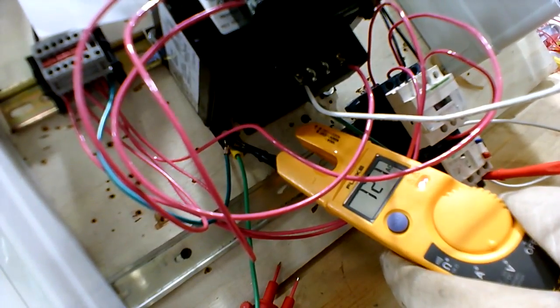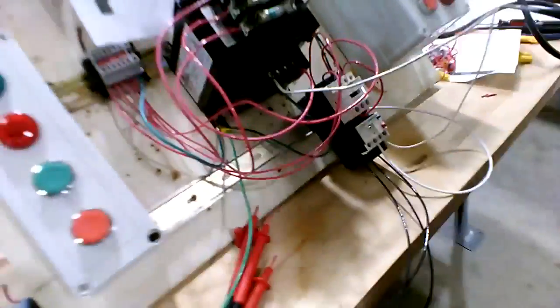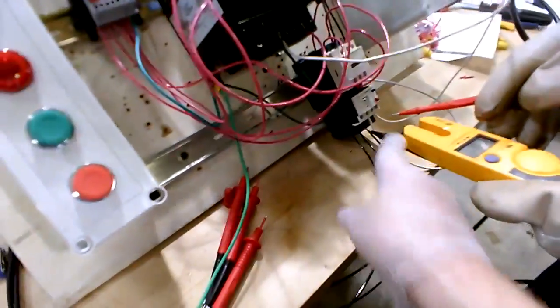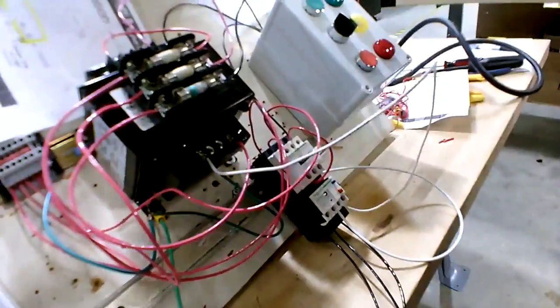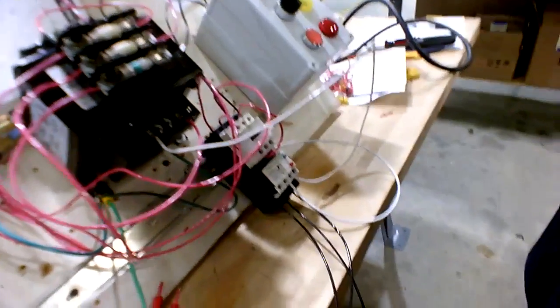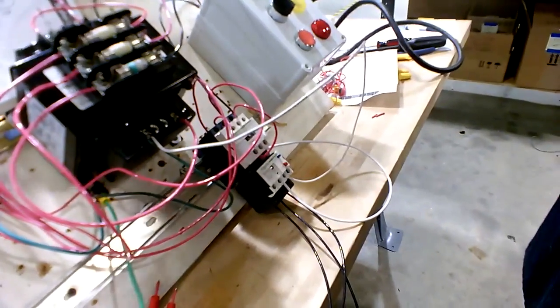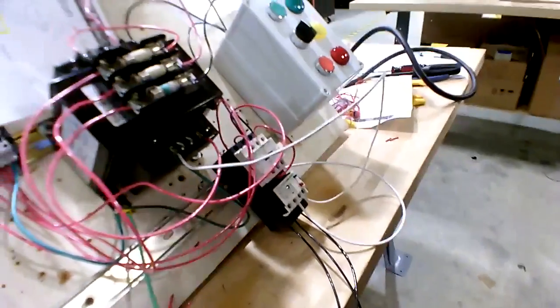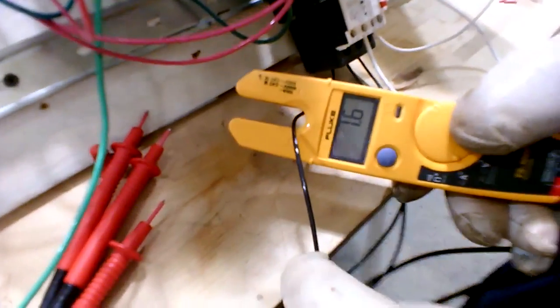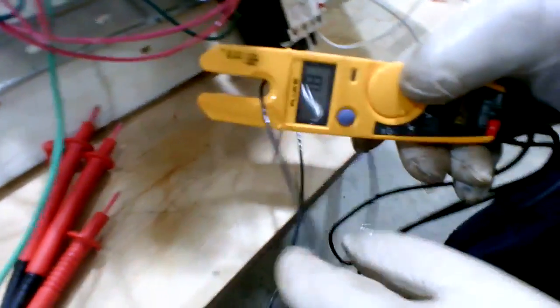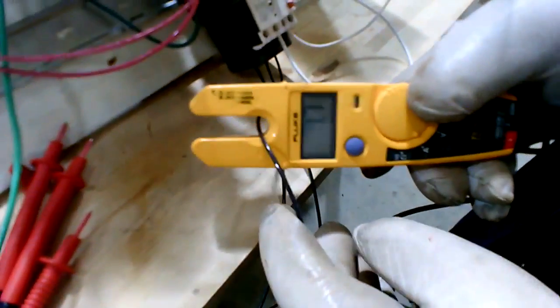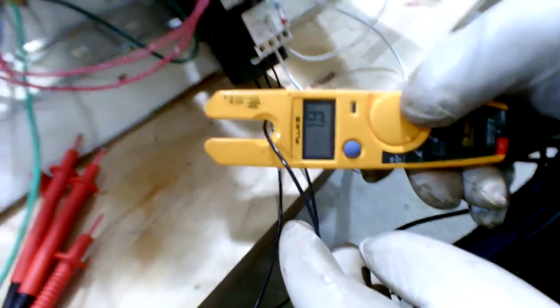That's correct. Now you're going to check the amps. So you checked voltage. To check the amps, you go to A, and you put the plug back in the back of the meter and use the port for the pickup. It's a current pickup that you use to check amps with. You don't use the probes on this meter. So you put each lead inside that magnetic pickup. It's 1.6 amps for leg 1, leg 2 is 1.8, and then 1.7 there. So that's pretty good.